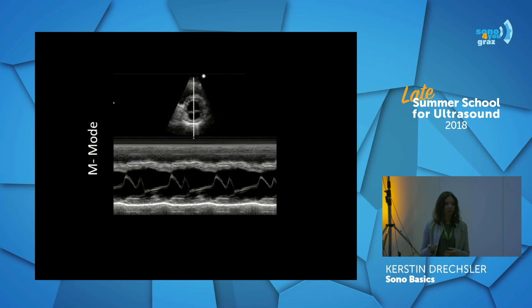As we are scanning, we have to have transducers, and there is a wide variety of transducers, and we always have to choose the appropriate one. The transducers vary not only in their shape and size, but also in their frequency. And something we have to keep in mind is that high frequencies will result in a really good resolution, and low frequency probes will result in a relatively bad resolution. But as a drawback, high frequency probes have a very low penetration depth, so they get attenuated relatively quickly. And low frequency probes, as an advantage, have a very deep penetration depth.